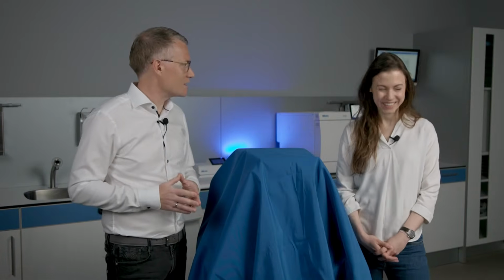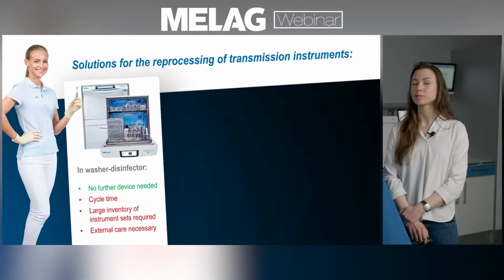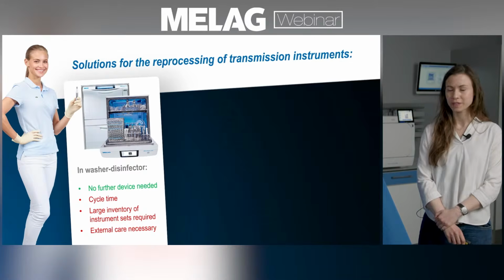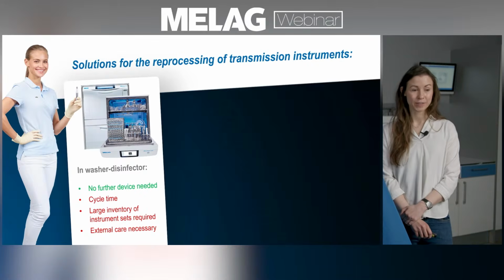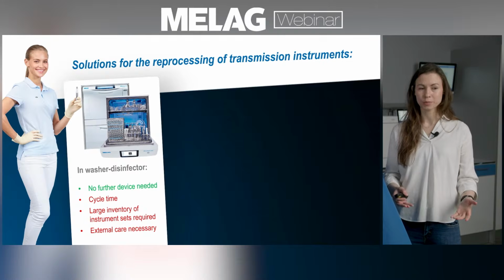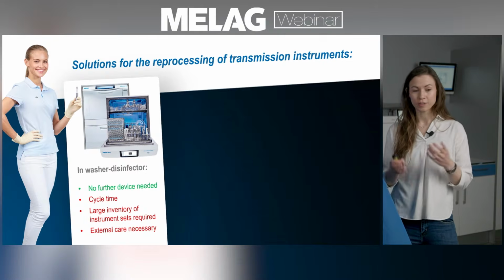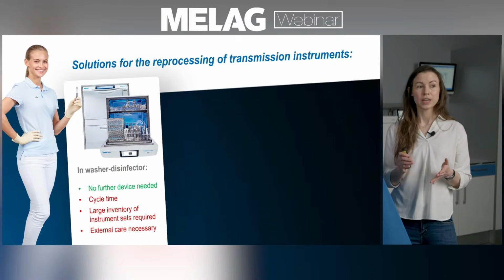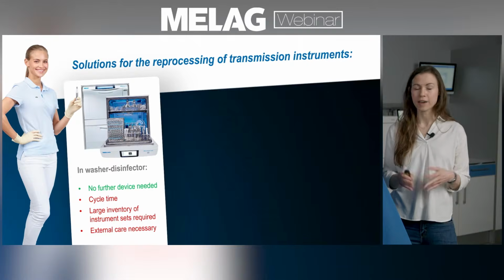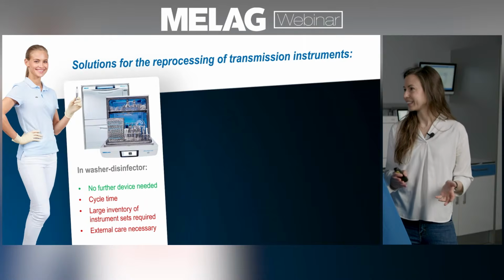Right now, I would like to focus very clearly on the cleaning and disinfection point. If we take a look inside dental practices and in clinics, there are several solutions for how you can actually do the step of cleaning and disinfection. Maybe you can tell us a little bit about it. The first and classic approach would, for example, be using a washer and disinfector for the reprocessing of your instruments. The major advantage here is, of course, you reduce the workload for your practice. It means that you have a larger device where you can not only put your handpieces in, but also the other instruments and have them automatically cleaned. That means you don't need an extra device for the cleaning of your handpieces.